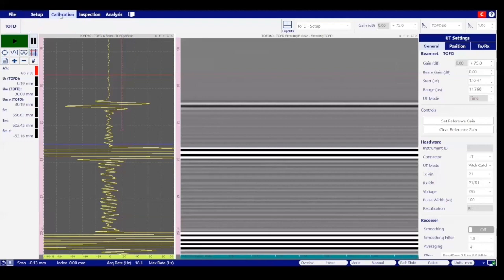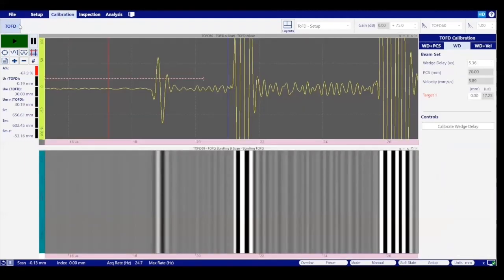Similarly, the TOFD calibrations. As you see here, when we choose the TOFD setup, the calibration options have been changed to show the ones which make sense or which are required for TOFD. So we can either calibrate wedge delay, PCS, and velocity.